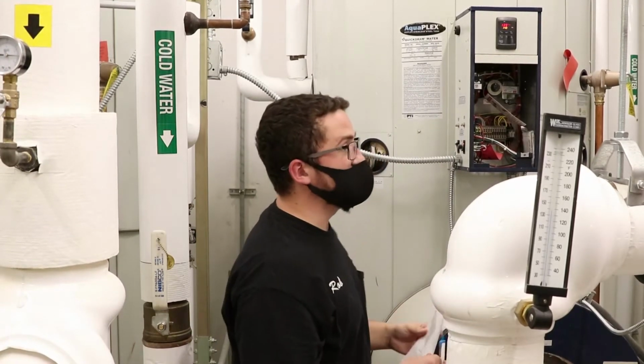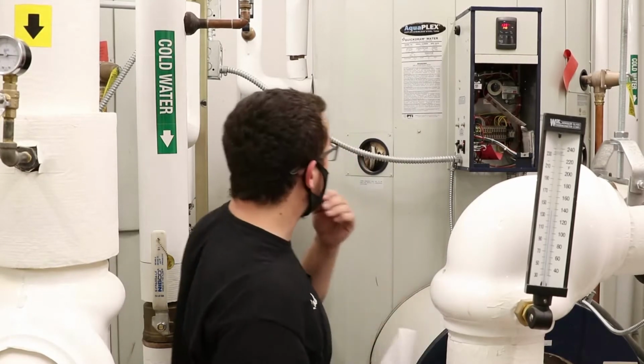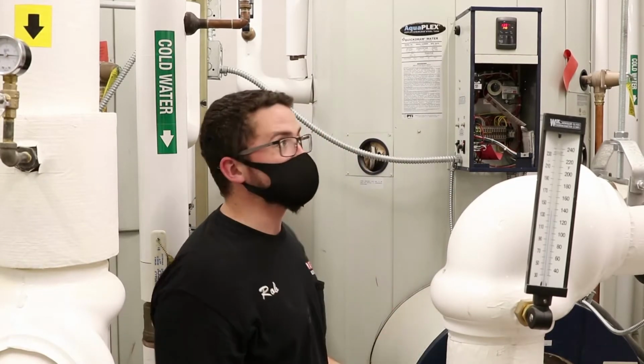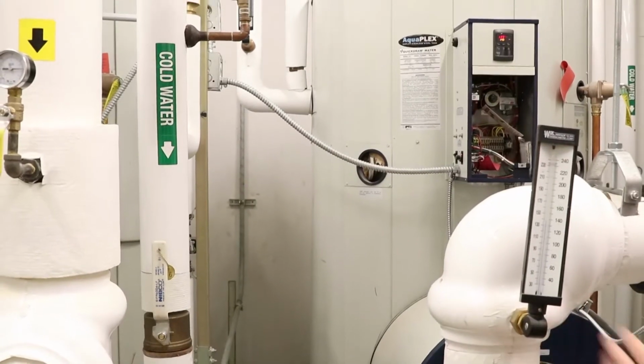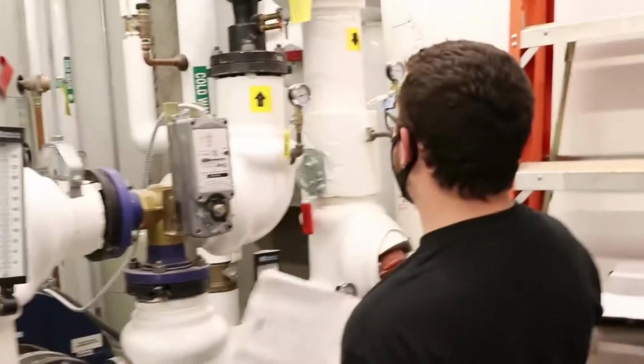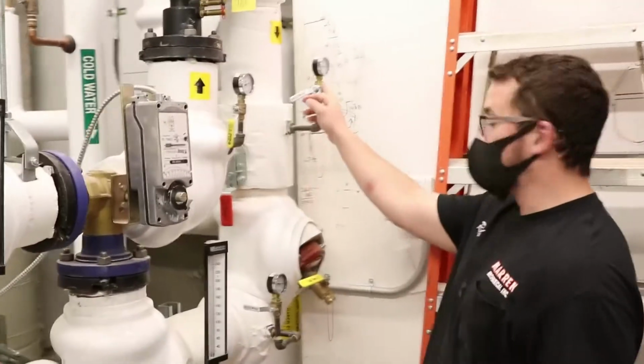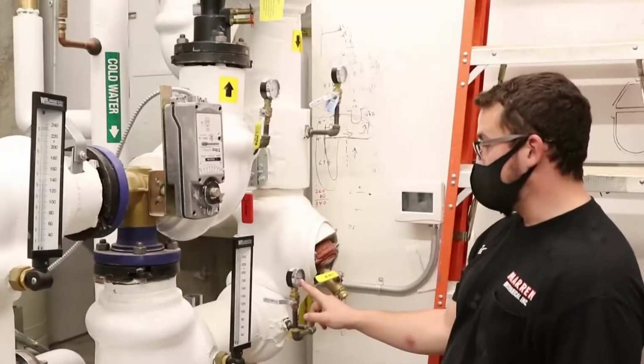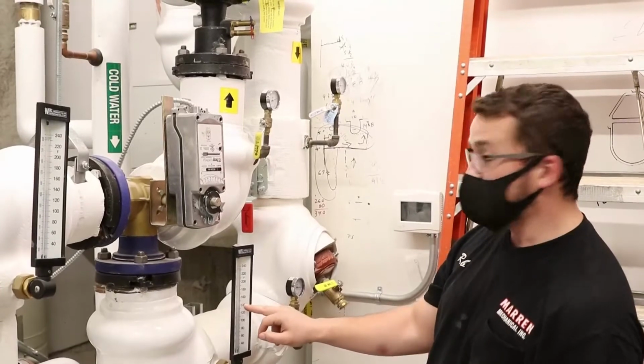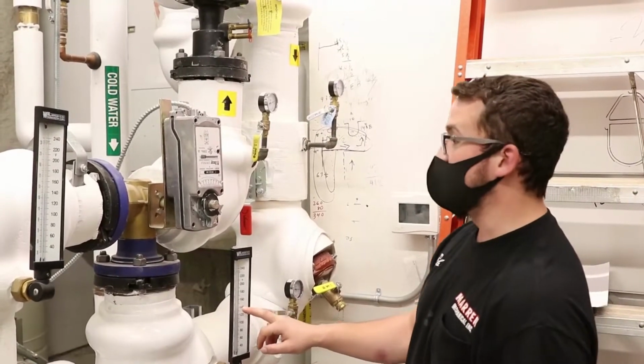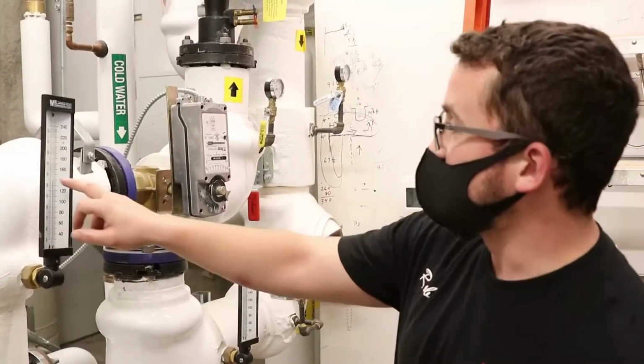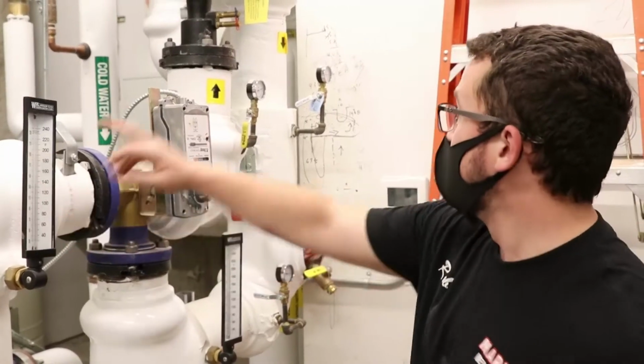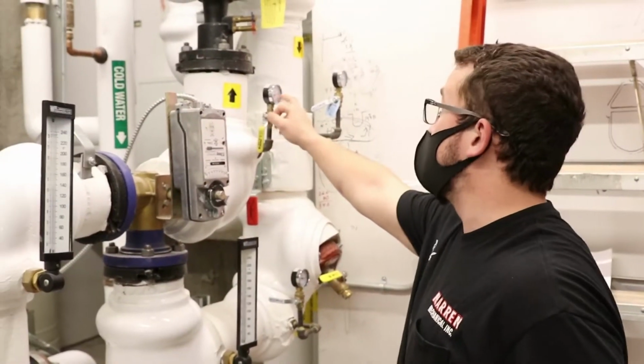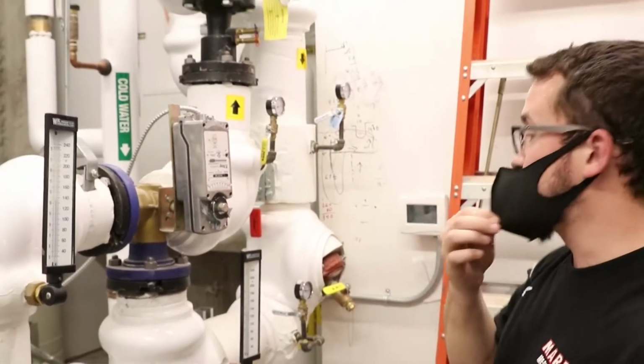So at least monthly, if not more often, you should check these things for accuracy like I just touched on. You should get used to what these numbers are on these gauges. This is telling you the water pressure coming into the heat exchanger, the water temperature of the boiler water coming into the heat exchanger. Here's the temperature of the water leaving the heat exchanger and the pressure of the water leaving the heat exchanger as it goes back to the source.